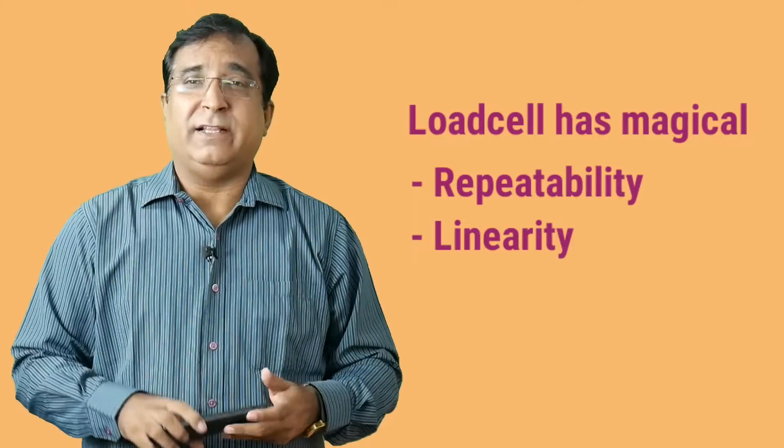There are two characteristics any load cell can have: the repeatability and the linearity on which you can blindly trust. This linearity is maintained from few grams to thousands of tons and it is maintained for years as long there is no disturbance in load transfer mechanism or problem in load cell alignment.